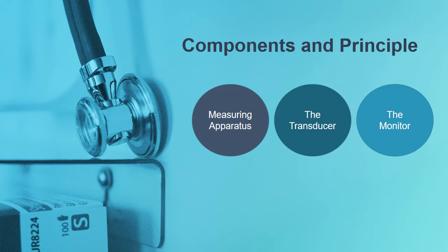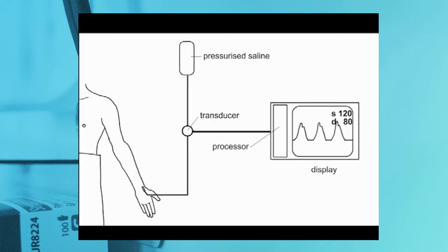The components and principle of arterial blood pressure monitoring are divided into three parts: measuring apparatus, transducer, and monitor. The measuring apparatus is the whole system of the arterial line. You can see a patient with a radial artery cannulated, directed through a transducer and then a processor to a display system on the monitor, along with a pressurized saline bottle. The transducer must be placed at the level of the patient's heart — this is a key point. If the patient is propped up, you must reposition the transducer accordingly.